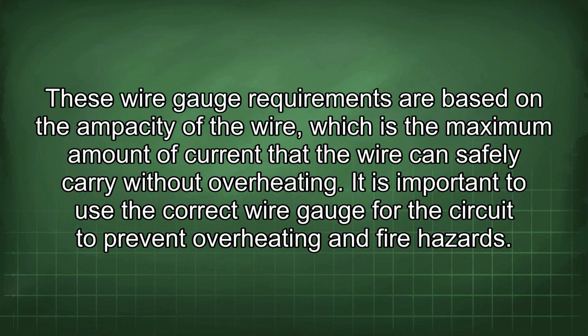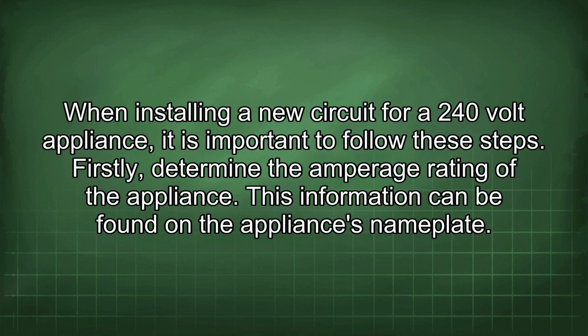These wire gauge requirements are based on the ampacity of the wire, which is the maximum amount of current that the wire can safely carry without overheating. It is important to use the correct wire gauge for the circuit to prevent overheating and fire hazards. When installing a new circuit for a 240-volt appliance, it is important to follow these steps.